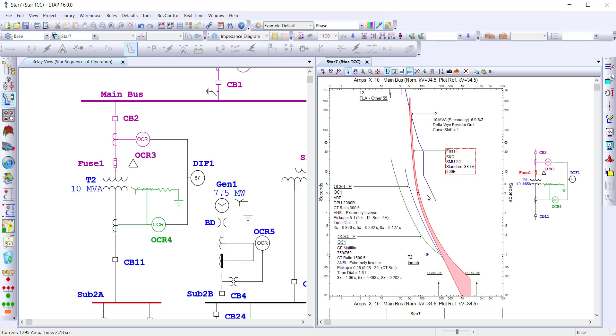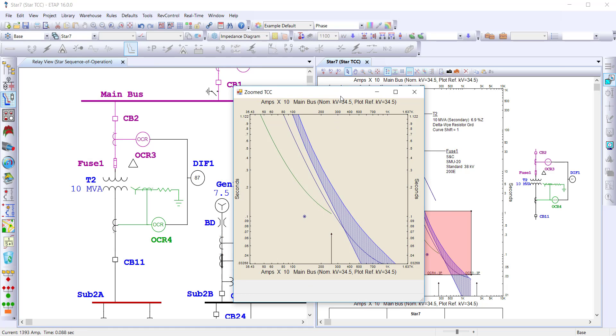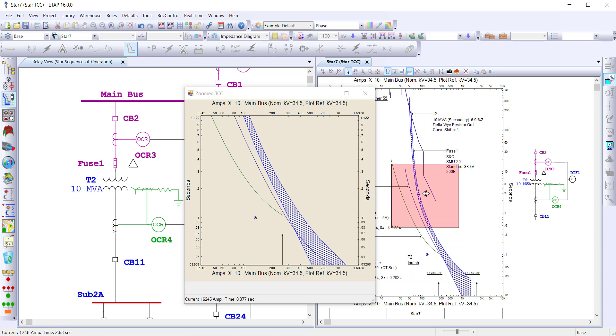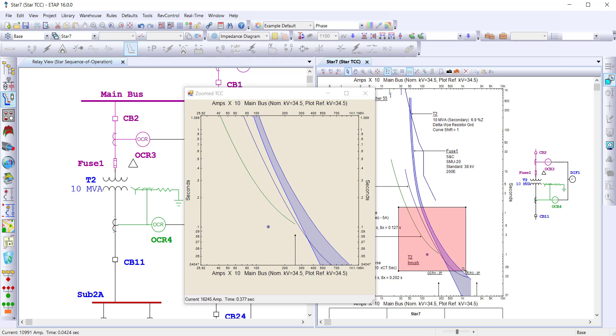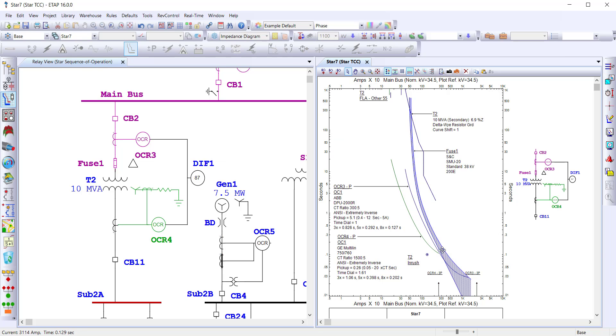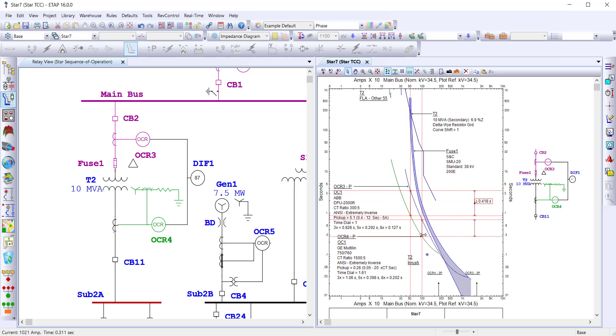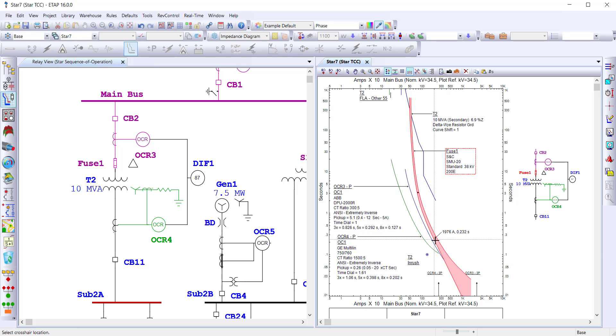Other tools are available to make doing a coordination study easier. You can zoom in to a new window, and the zoom window dynamically updates as you drag it across your TCC study. Or find the time difference between any two curves, and drag that, dynamically adjusting the time difference. And if you want the specific time and current at any point on the curve, select the first curve and bring in a crosshair to give you the exact time and current at any point.